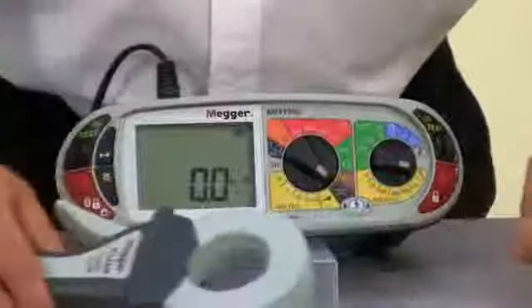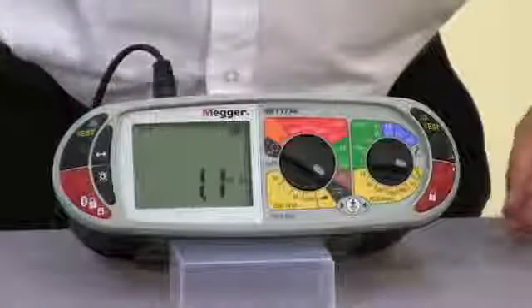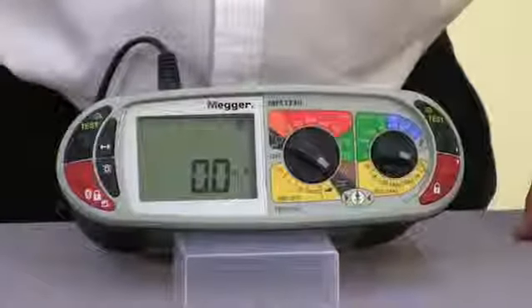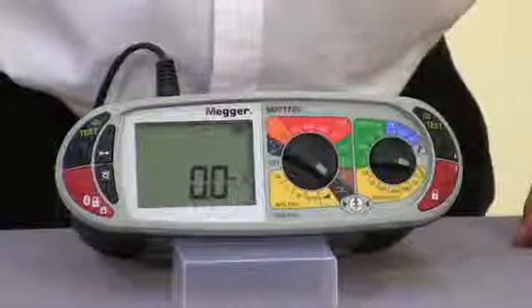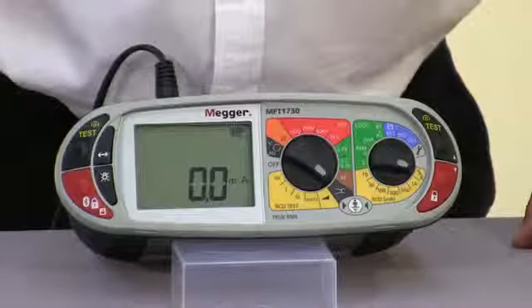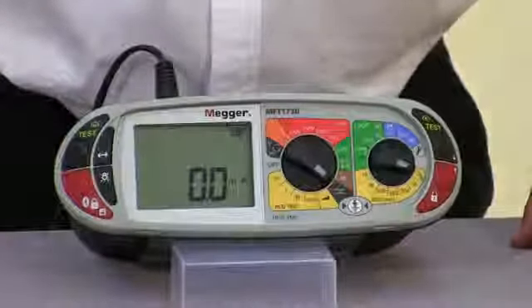The MFT1720 and 1730 models also have the facility of a CT input. Now the current transformer that we have available as an option has a special input plug, and this unit, the Megger I-clamp, will actually measure not only high current, so you can use it for load measurements or diversity measurement, but will also measure down to very low milliamp leakage values. This means that it can be used to identify if you've got a circuit with a particularly high earth leakage in the event of nuisance tripping.